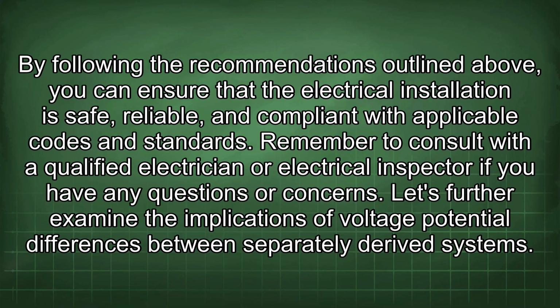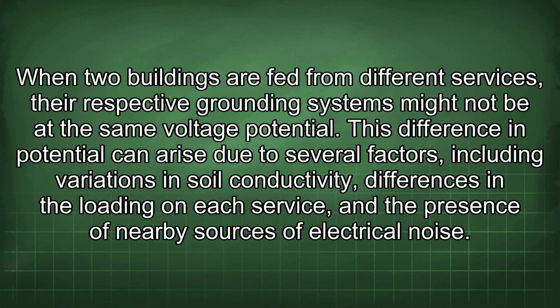Let's further examine the implications of voltage potential differences between separately derived systems. When two buildings are fed from different services, their respective grounding systems might not be at the same voltage potential. This difference in potential can arise due to several factors, including variations in soil conductivity, differences in the loading on each service, and the presence of nearby sources of electrical noise.